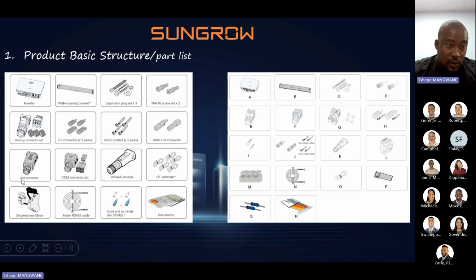We do supply a grid connector cover on your grid input terminal side. The COM connector set is where we connect our RS-485 communication and also our CAN bus cable for battery connections. The WiNet-S module is our Wi-Fi dongle, which we use for the iSolarCloud integration as well as commissioning the system, but I will touch base on it.